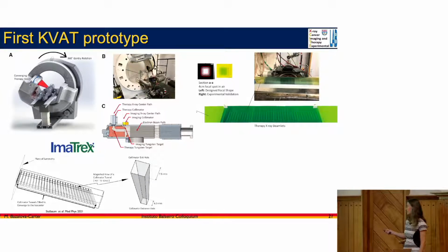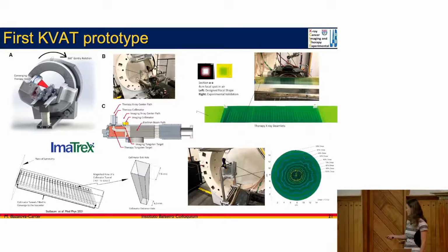This is just a simulation or schematics of the focal spot and its measurement on a film. And they have done a number of validations. So they basically positioned a phantom around the gantry. They could rotate the gantry, and they could deliver 360-degree delivery around the phantom. And you see the dose distribution is superimposed, and with a little bit of squinting, you can see that the 20% isodose line is on the skin and 100% isodose line is in the center. So even in this case, but again, for a smaller phantom, they were able to achieve this 5-to-1 target-to-skin ratio.